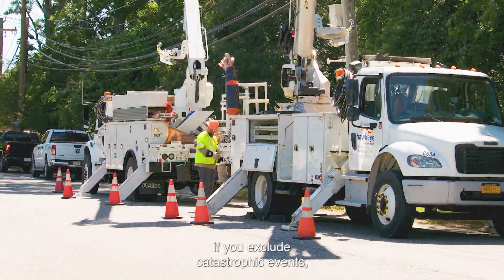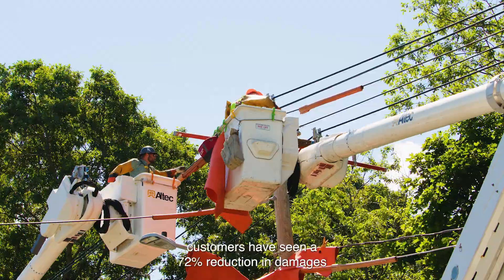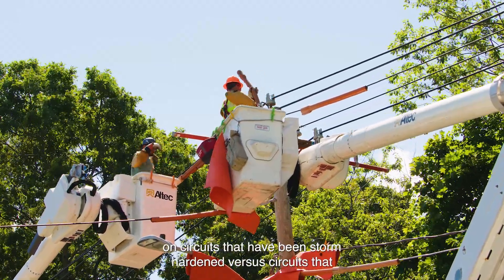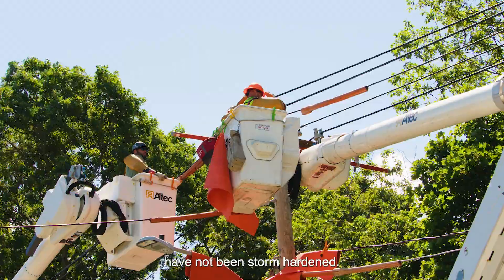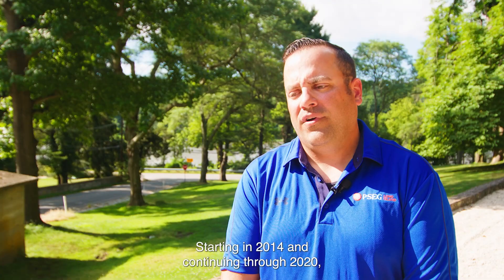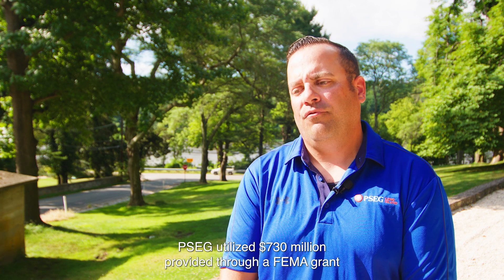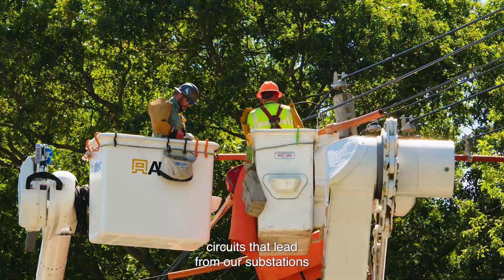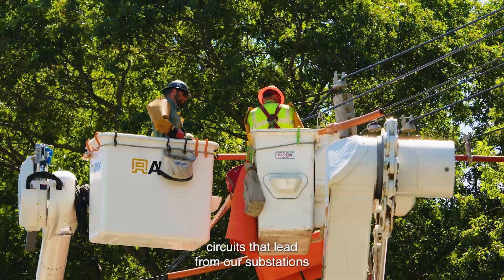Customers have seen — if you exclude catastrophic events — a 72% reduction in damages on circuits that have been storm-hardened versus circuits that have not been storm-hardened. Starting in 2014 and continuing through 2020, PSE&G utilized $730 million provided through a FEMA grant to storm-harden our mainline distribution circuits that lead from our substations out to our customers.